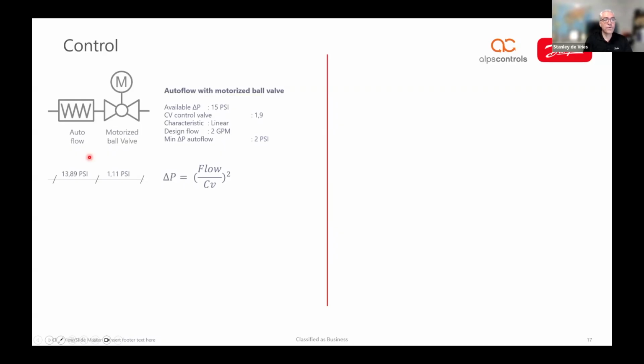Let's say it's usually start-up times in the morning, when you're going from night setback. So let's be generous, it will be 5% of the time that your system will be running on full load. Which then means that 95% of the time it's running in some kind of partial load. And specifically, if you want to modulate, you want to be able to give your air handling unit or fan coil unit or whatever also 50% of the flow, or even less, 20% of the flow. So now what happens when you start to close the valve?